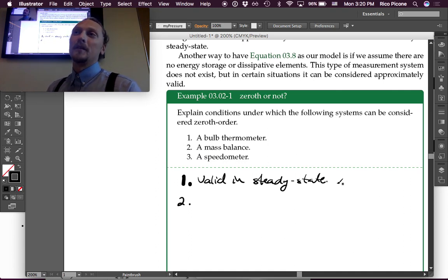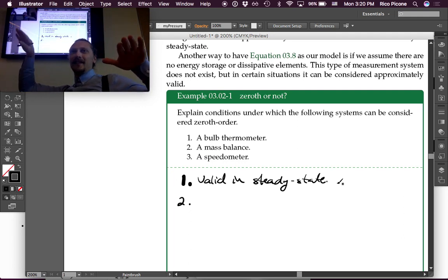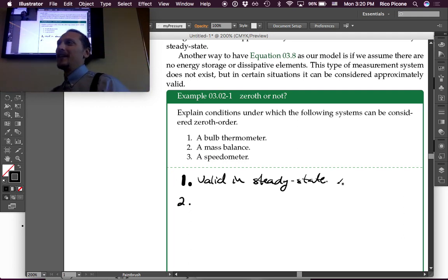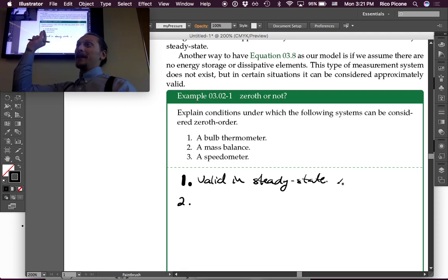I don't know if you guys have ever dropped a small weight on a mass balance and had it react? Yeah, kind of wobbles. Yeah, it kind of does this, right? So the ideal would be if you were to place a 20-gram weight on the mass balance, it would immediately show 20. It's like when you're stepping on one of those old gym scales, you know, you go weigh yourself to find your body fat percentage. It has a tendency to wobble. You're trying to adjust it. The ideal would just be instant. Yeah, it would just instantly be at the value. The readout would be there.